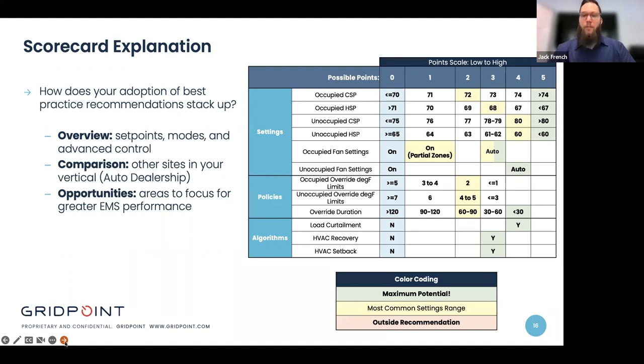We talked about overrides as well. Best practices for overrides: try to limit the use of overrides and use them during extenuating circumstances, but try not to return to the thermostat every hour or every 2 hours, or whatever it is, periodically to override the unit. Put in appropriate set points based on best practices and use overrides when there's some outside source impacting your site's comfort level. Then finally, adopt the algorithm. Being able to transition as efficiently as possible and avoid unnecessary HVAC runtime is crucial to making sure that you keep track of your HVAC health.